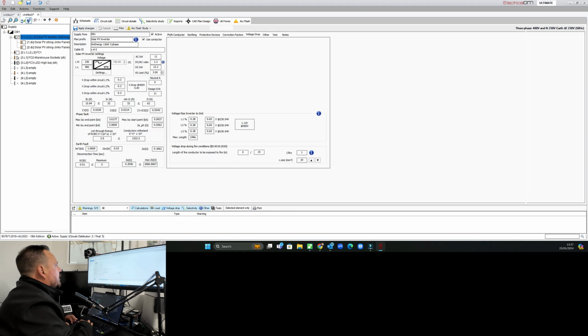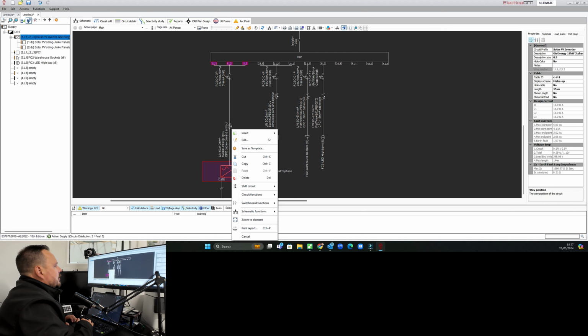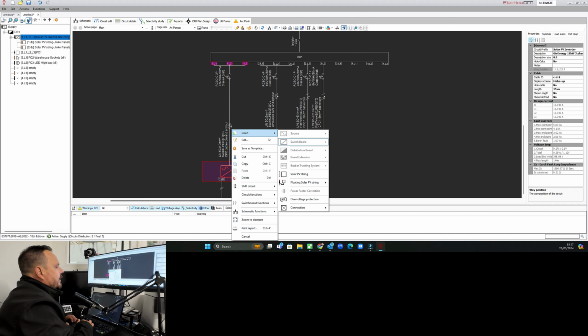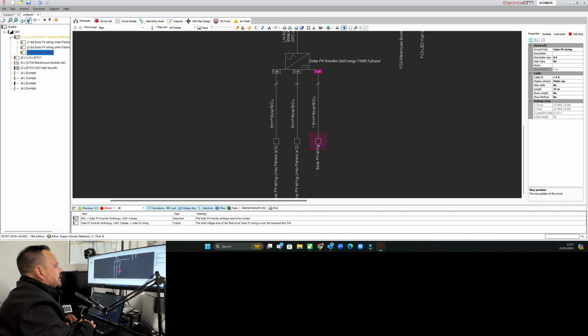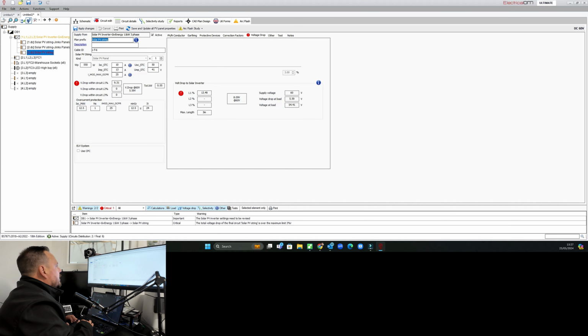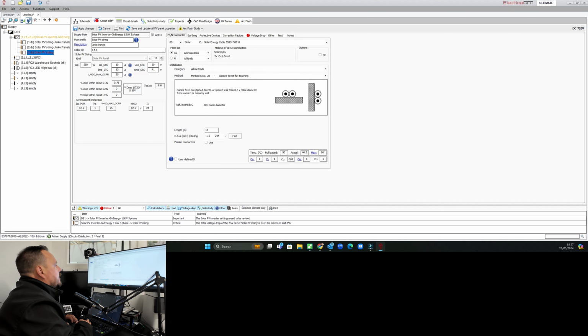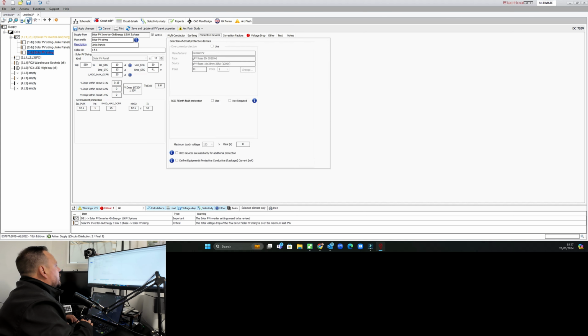We can add another string if we want. So we have a super duper inverter, and we're going to pop another PV string on. Again, we can click into here, and we can call it Jinko panels just because they're all Jinko panels. Why not? And again, we'll set it to 12, 3 equally sized strings. If we go back to our phase, neutral and earth conductors, we set those to 6mm. And again, we'll say they're clipped direct on the system.